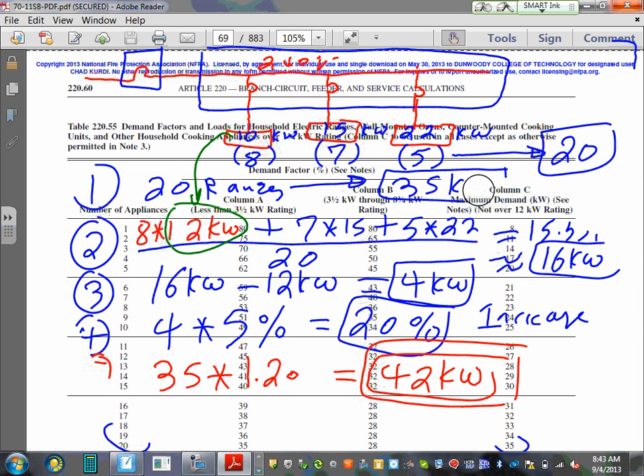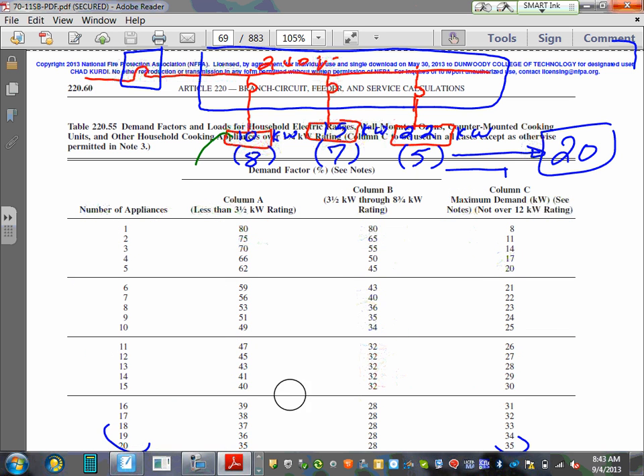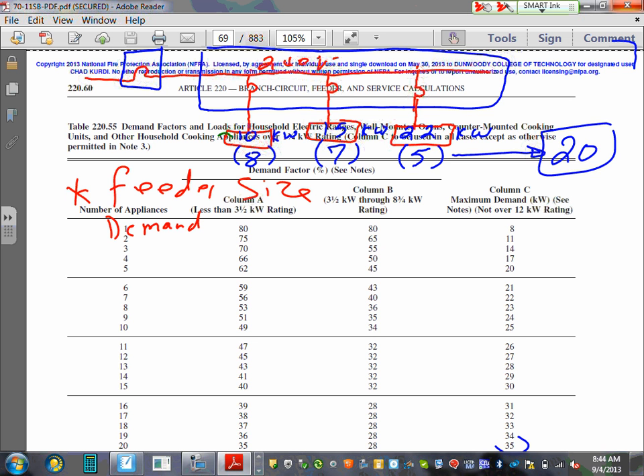So I want to go all the way here. Oh, okay, good. And I'm going to go right here. Okay, now we did that. Now we found our demand. Now let's go size the feeder. Feeder size. Okay, what was the demand? 42 kW. Then I need to do the calculation based on 42. So 42 kW demand.